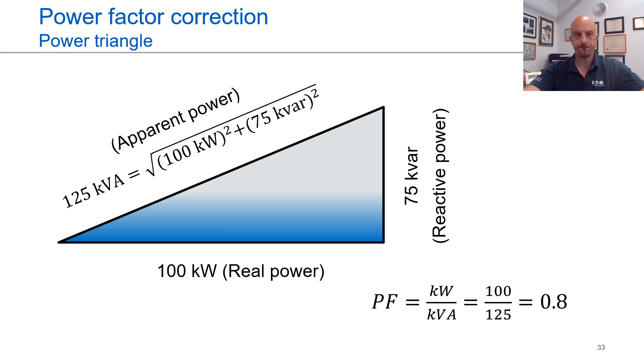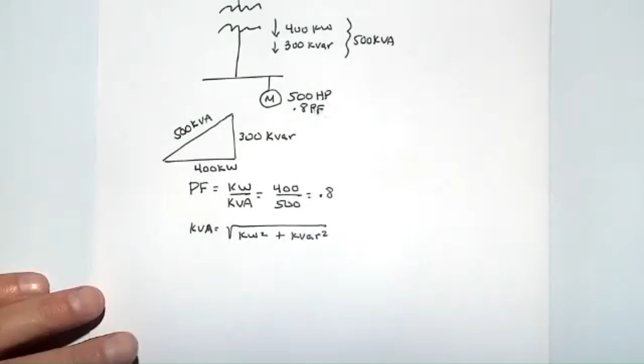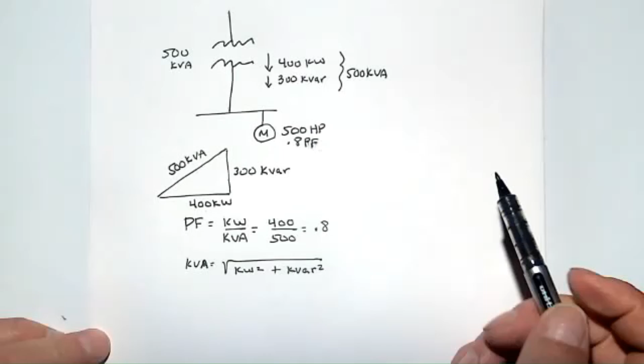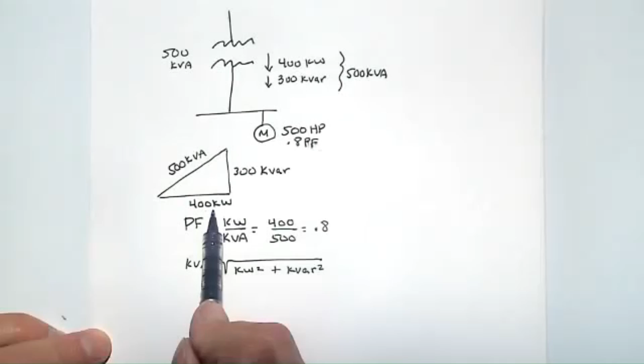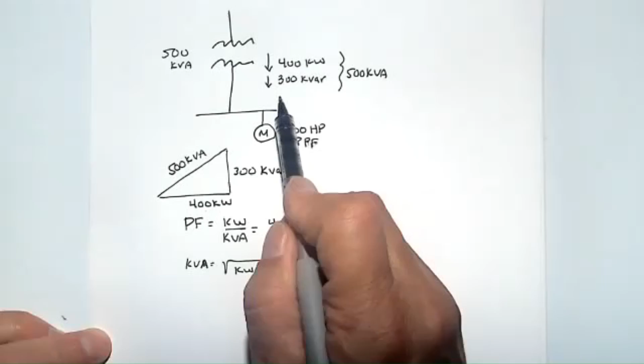Okay, for the last example, we're going to give you an example of power factor correction and how you would apply capacitors to correct for a power factor so that you could add more load. In this case, we have a transformer that's 500 kVA rated, and it has a 500 kVA load flowing through it to this motor, 500 horsepower, 0.8 power factor. So at 0.8 power factor, our kilowatts are 400, our kVAR are 300, and our kVA again is 500. So that's what's flowing through the transformer right now.